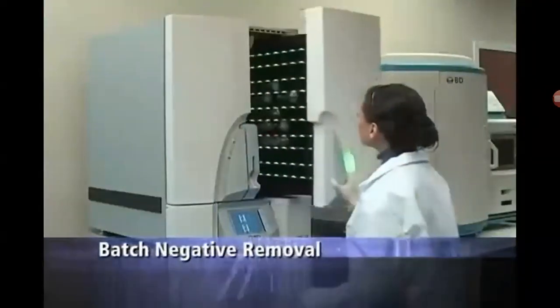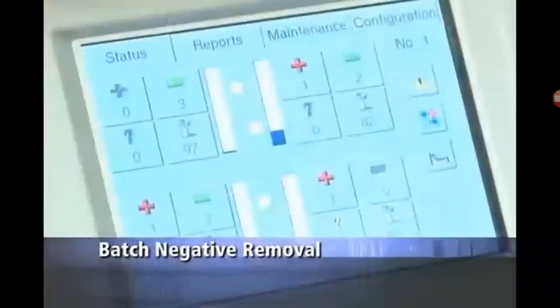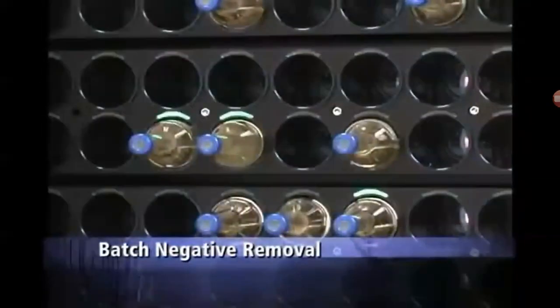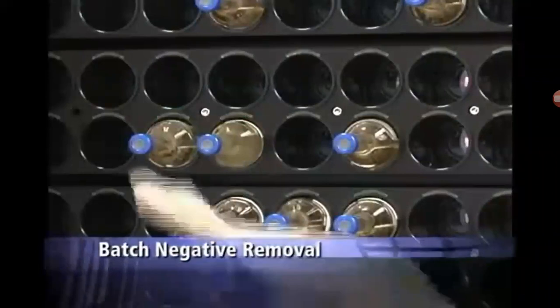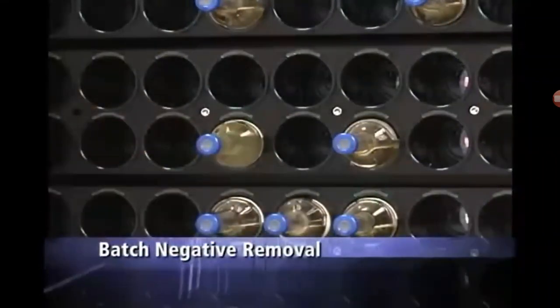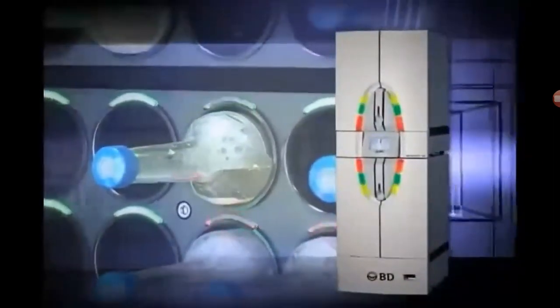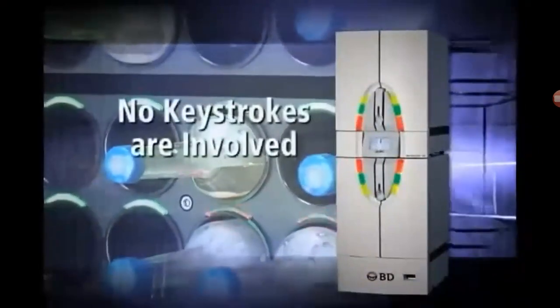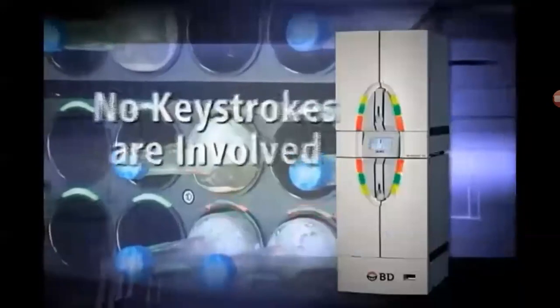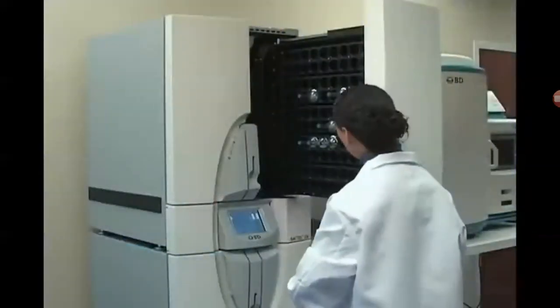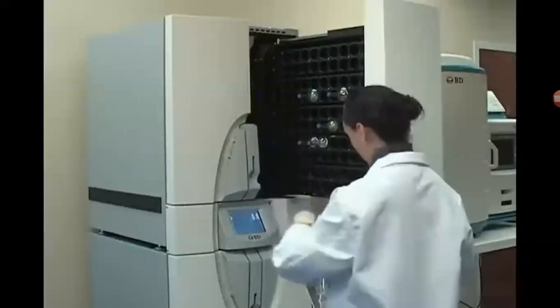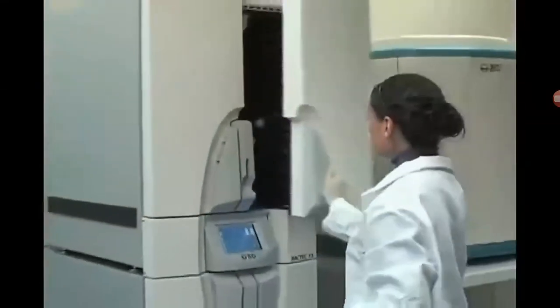Do you need to remove your negative vials first thing? A negative indicator light on each drawer is automatically lit when there is a negative vial in the drawer. When that light is illuminated, simply open that drawer. Then choose a station that has a flashing green light indicating a negative vial and remove the vial. With that action, BACTEC FX automatically goes into the workflow for removing negatives and lights up only those stations that contain negative vials. No keystrokes are involved. Simply finish removing all of the negative vials. A triple beep informs you when all of the negative vials have been removed. And when it comes to removing positive vials, you'll see that it's just as easy.